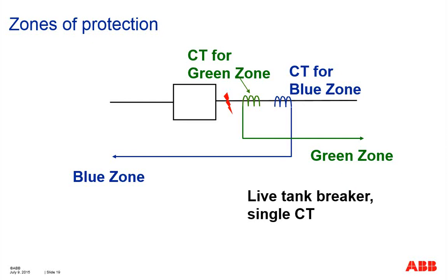However, if you need prompt, instantaneous bus bar protection for this fault, then you need some type of logic, or what we call end zone or blind zone protection, which we will introduce later. Again, that's when the breaker is closed.